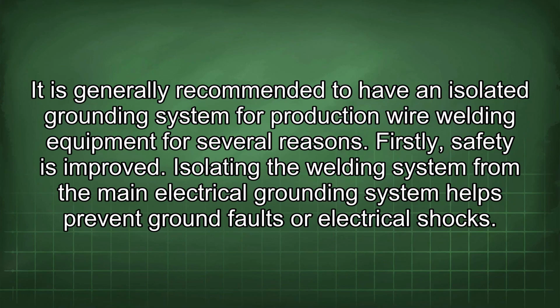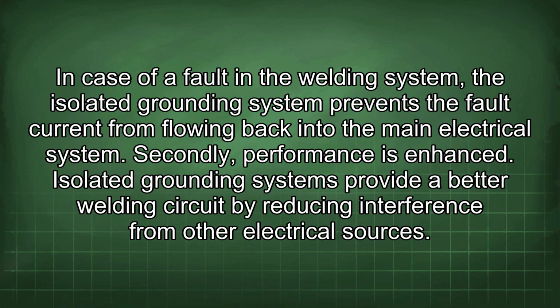It is generally recommended to have an isolated grounding system for production wire welding equipment for several reasons. Firstly, safety is improved. Isolating the welding system from the main electrical grounding system helps prevent ground fault or electrical shocks. In case of a fault in the welding system, the isolated grounding system prevents the fault current from flowing back into the main electrical system.